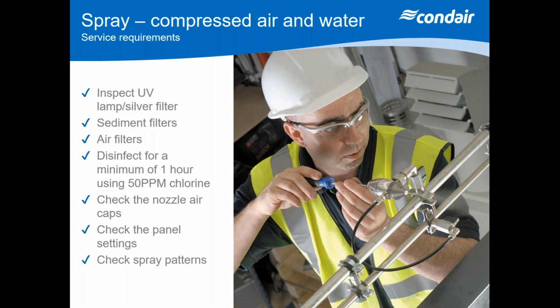Also, we'll have a UV change annually, as we've said before. Some of these systems may also have a silver filter, which you replace depending on the size of the system. It could be 6 months or it could be a year. And off the back of those, you'll have sediment filters to prevent those quartz sleeves from coating up with scale. We'll also have an air filter on the air pressure side that will need to be replaced every so often. So we'll inspect that as part of our general maintenance.